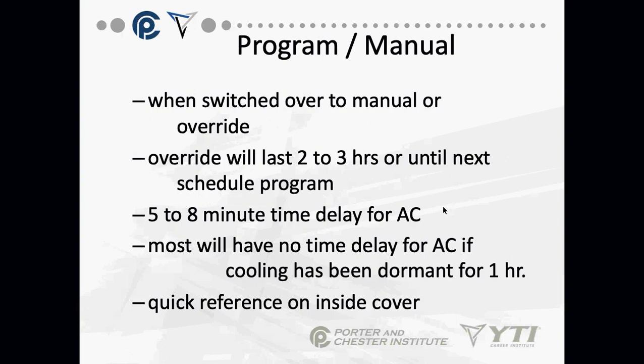Okay, the one thing I want you to remember on digital thermostats is there's a 5 to 8 minute time delay built into these things for the outdoor unit, for the compressor, for the condenser. Okay, 5 to 8 minutes. So if you're servicing the equipment and you turn the thermostat power off, and you service the equipment and turn it back on to test it, you get to wait between 5 and 8 minutes for that thermostat to say, okay, we can start air conditioning. Okay, because there's a 5 to 8 minute time delay. This is very frustrating, and there's really a lot of times no way to bypass it.